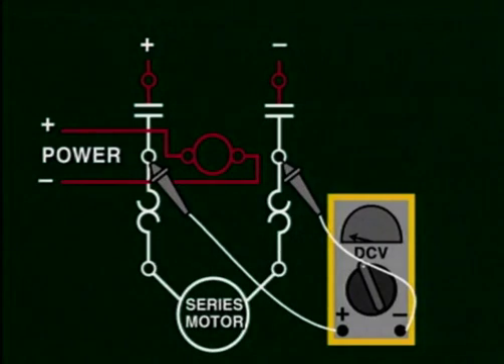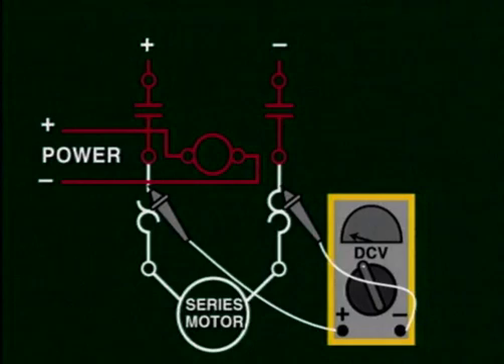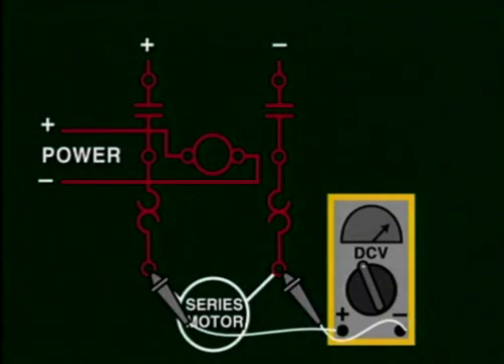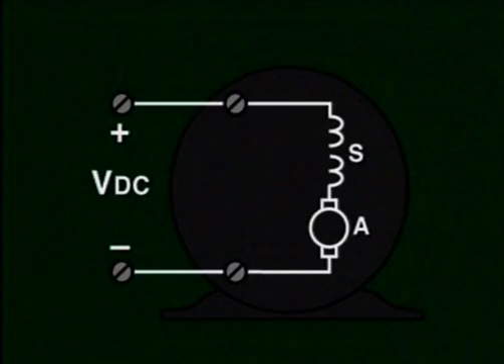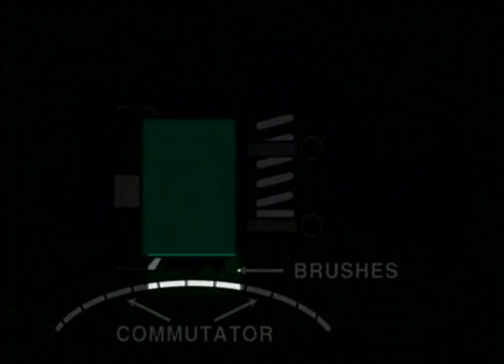If there is power after the power contacts, then check at the point before the overloads for voltage. If no voltage is present, then there could be a problem between the supply side of the overloads and the contacts of the starter. Check also to see if the overloads have been tripped. If so, you need to reset them and make note that something in the system has caused them to trip and you need to investigate it. If there is voltage at the motor terminals but the motor is not operating, we can assume that the motor has an opening in its winding or between the brushes and the commutator and the armature.